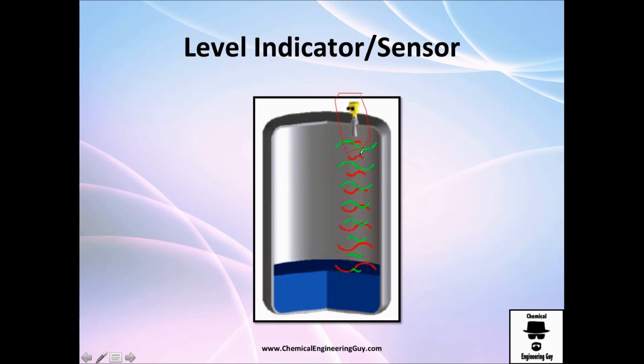Other fancy sensors, for example this ultrasonic. It sends waves right here, then they bounce, and the time required to do that divided by two and multiplied by the velocity will give you the distance, which is the height. The height will show you the level.